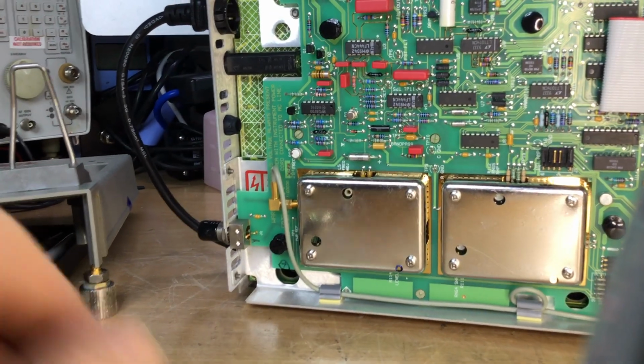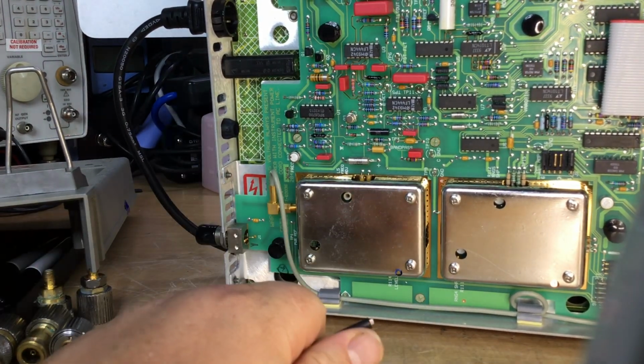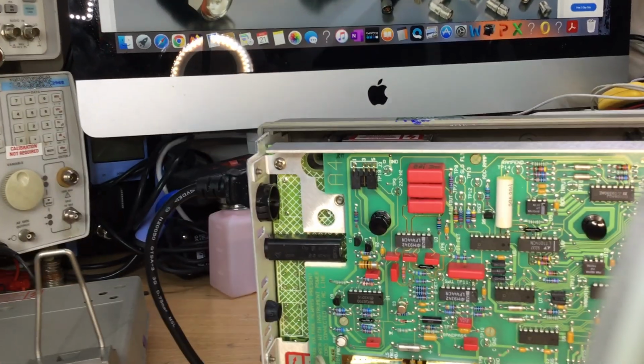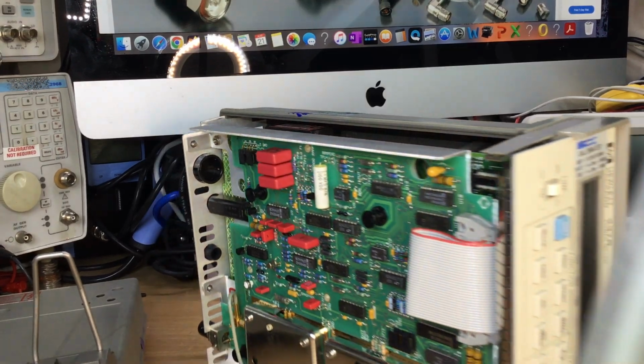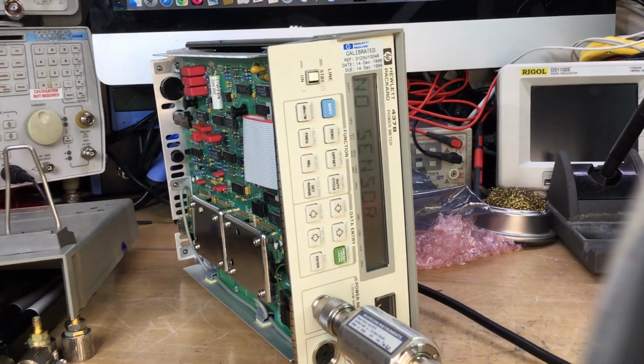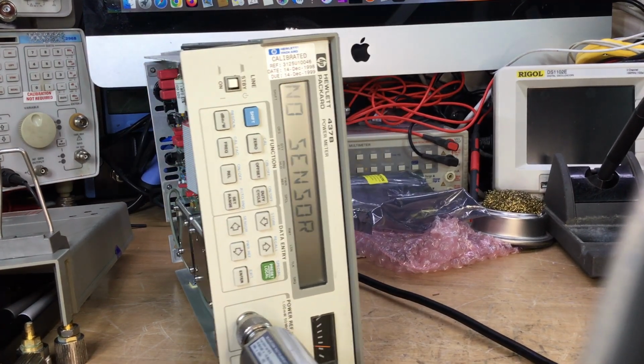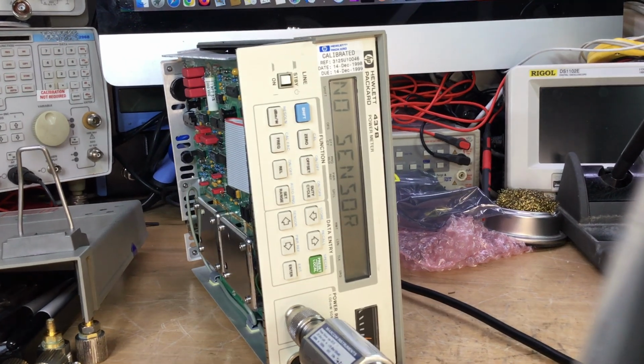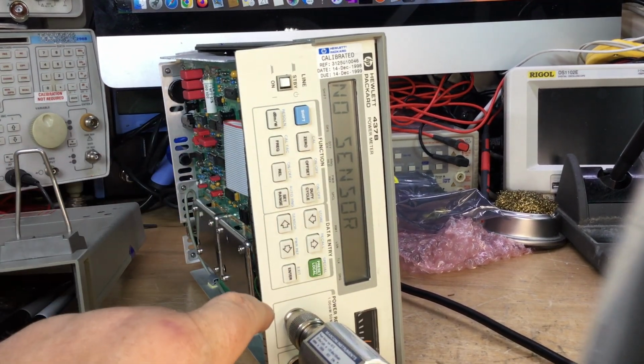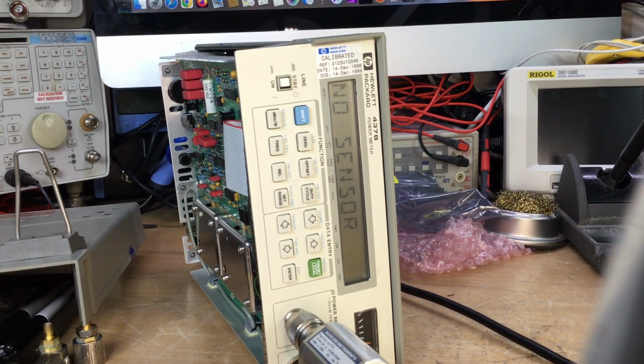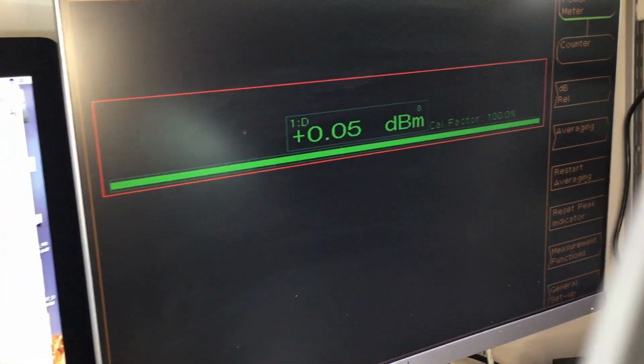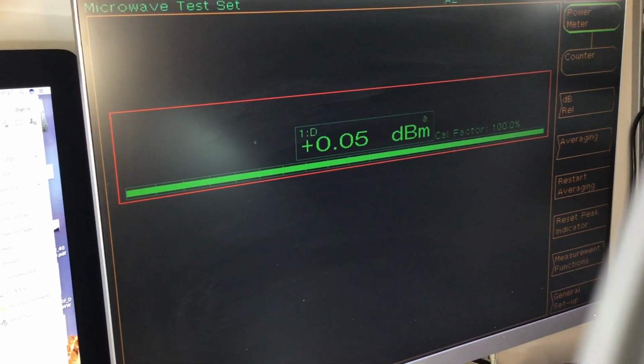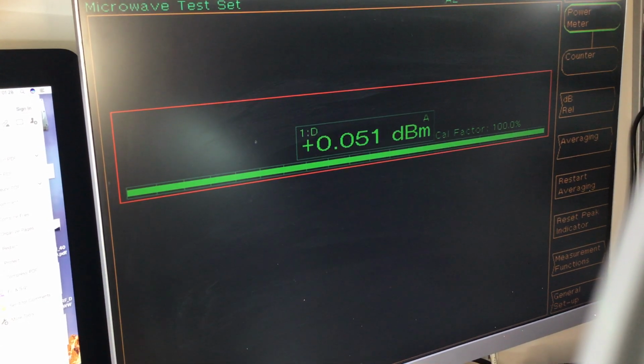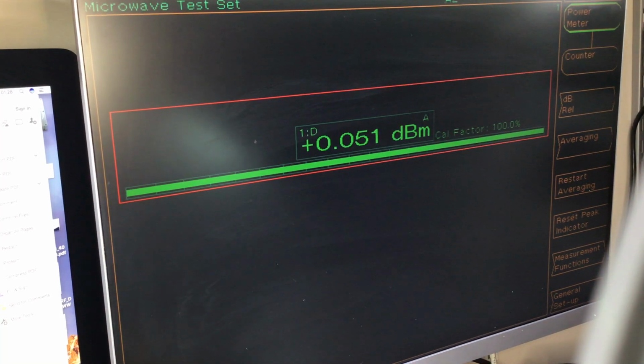So that's what we're going to be adjusting using our trimmer tool, and we're going to switch the RF output on by going across to the front here, and I think at the moment it says no sensor or something. So we switch on the cal output by doing the shift and then this key here, and that switches on the calibrated output. So if we then go to the power meter reading on the microwave test set, what we're going to try and do now is adjust that potentiometer that we've just seen for as close to 0 dBm as we can.